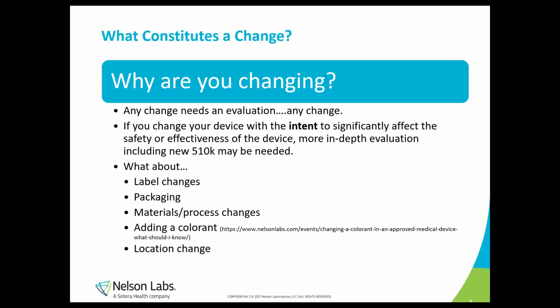Another change that some people don't realize can have a big impact is packaging. The type of residuals that can come from sterilization and other processes, including packaging, that can be leached from that and put on the device, can have an impact. Now that we're doing more extractables and leachables testing on these medical devices, the more we're seeing chemicals coming from packaging and then getting onto the medical device. So if you're changing your packaging materials or even setup, those evaluations need to happen.